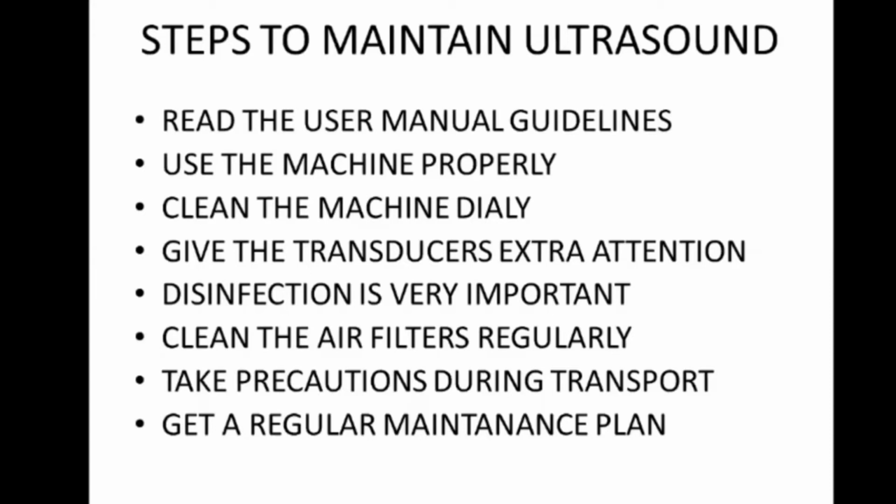The only problem with the ultrasound is that sometimes there will be an issue in the probe. He tends to change the layer of the probe, or change only the crystal inside the probe, but the machine will be working fine. So it is the care that we give to the ultrasound or any machine at all. If we don't maintain it properly, automatically the durability of the machine will come down. So these are the steps that you need to know to maintain an ultrasound. Then we move on to the next slide.